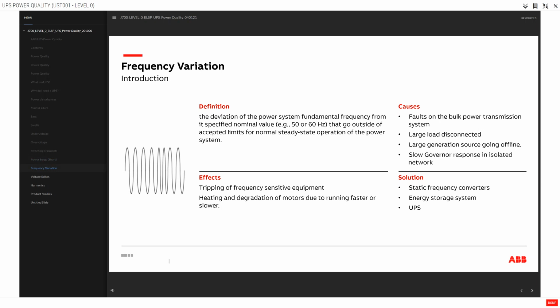Definition: the deviation of the power system fundamental frequency from its specified nominal value, for example, 50 or 60 Hz, that goes outside of accepted limits for normal steady-state operation of the power system. Causes: faults on the bulk power transmission system. Large load disconnected. Large generation source going offline. Slow governor response in isolated network. Effects: tripping of frequency-sensitive equipment. Heating and degradation of motors due to running faster or slower. Solution: static frequency converters. Energy storage system. UPS.